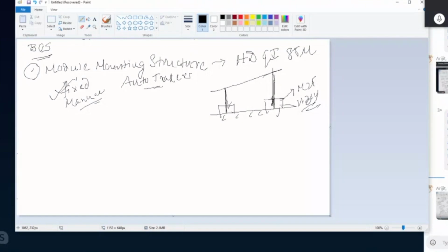Structure designing can be done in AutoCAD, which, though it's a mechanical design, we are not covering in our course. And as for strength, we generally say we need a structure for 140 km/h. That is the wind speed that it needs to sustain. So we can design a structure, and we can check the wind speed it can sustain in something called a STAAD report. Clear? So the wind speed that it can sustain, we can check from the STAAD report.